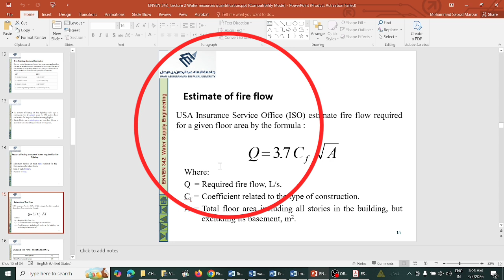CF depicts the coefficient of construction, and it depends on the type of building material. CF for wood frame is 1.5, ordinary is 1, non-combustible is 0.8, and fire resistive is 0.6. It means more combustible material leads to higher fire demand, and safer material leads to lower fire demand. A is the floor area, meaning the total floor area excluding the basement. So you don't have to add the basement. If the basement area is given in the question, don't include it.